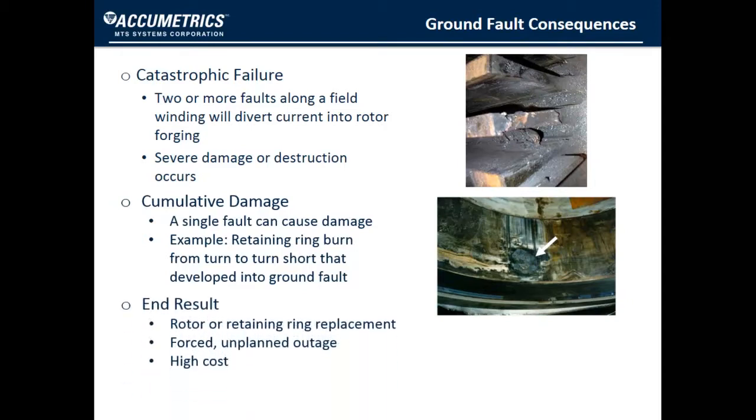You can see that in either case, single or multiple faults, you can have severe damage. If the rotor should need to be replaced, it would likely mean a long forced outage which often comes at a high cost. For this reason, it is very important that you detect the onset of ground faults.